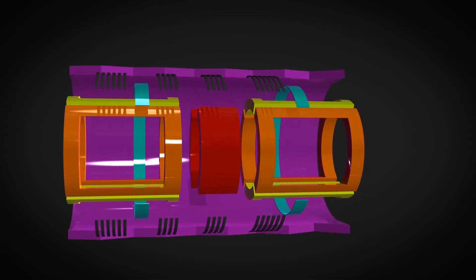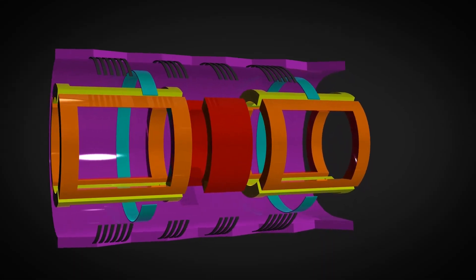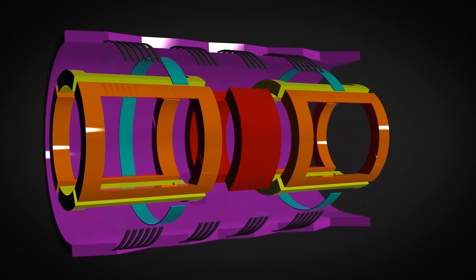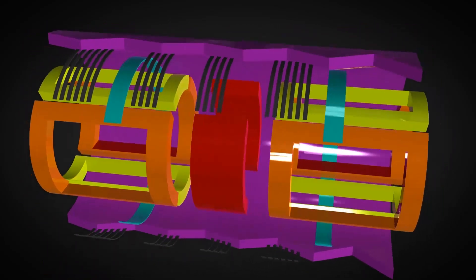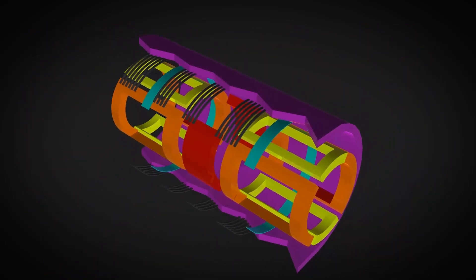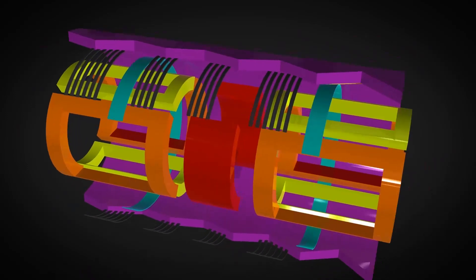A gradient coil is an independently energized coil that creates a linear gradient in a relatively homogeneous magnetic field. There are three different gradient coils located inside within the main magnet.